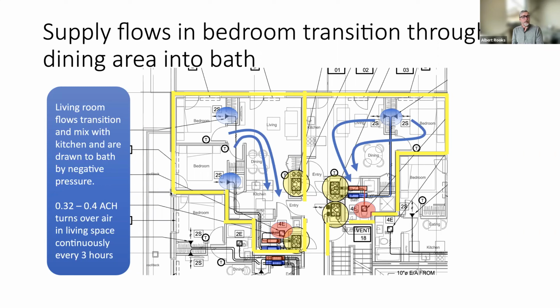Through the mechanical ventilation to the red area. And the red area is typically in a bathroom and around a kitchen. So we've got matching supply points and matching exhaust points, and we just flow 24/7. The amount we flow is a calculation based on the room and the conditions that we're in. They're pretty simple to do, and we'll probably take a look at those next.